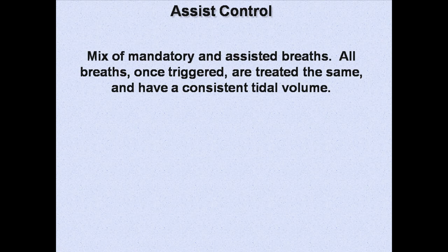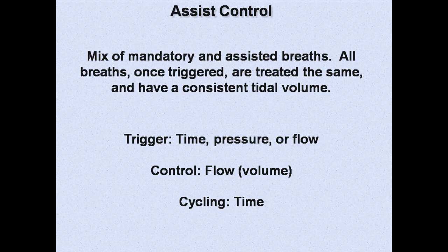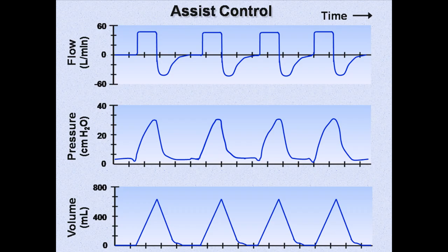The first mode I will discuss is assist control. This mode has a mix of mandatory and fully supported assisted breaths. All breaths, once triggered, are treated the same and have a consistent tidal volume. The trigger for assist control may be either time, pressure, or flow. The control variable is technically flow, though many people will refer to this as volume control, and the cycling variable is typically time. In assist control, the ventilator senses an inspiratory effort by the patient and responds to each by delivering a preset tidal volume. The patient is able to vary respiratory rate, but a backup rate is set to prevent hypoventilation.